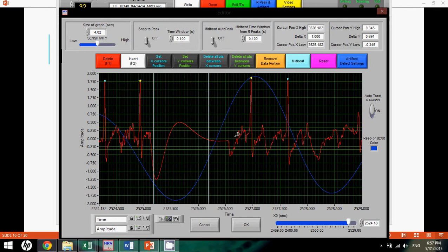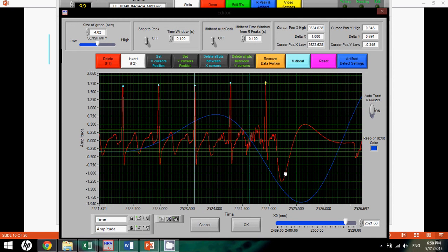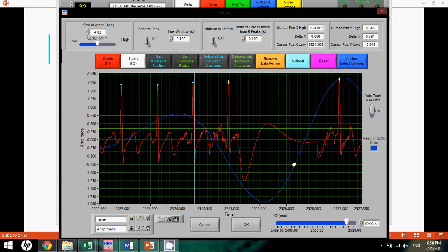Again, what we're going to do is come down here, and we can even measure this difference. One way to do this is simply to line up our channel, our R spike here, with the X cursor, and we can move our other one over to correspond to that X cursor as well. Typically, it's a good idea to leave at least 1 or 2 or 3 R spikes between your measurement and where it drops off. And once you get those X cursors lined up, you can come along here and measure.